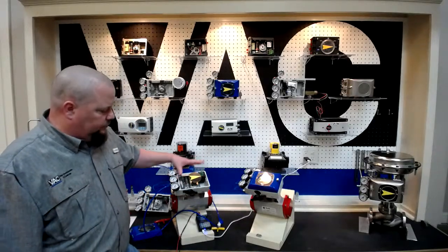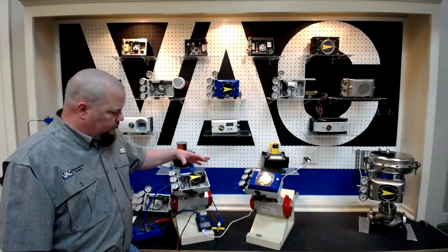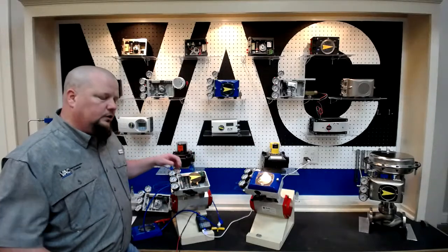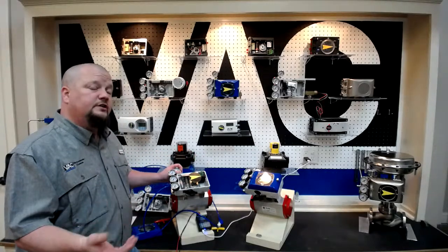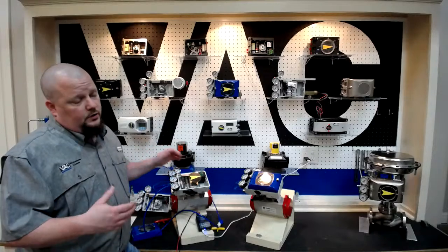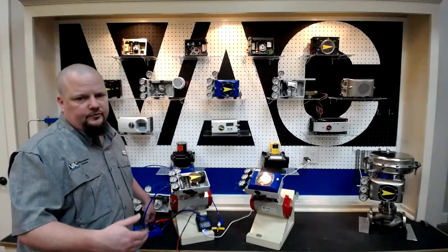So those are things we see a lot on the setup, and what those are basically: no signal, no air, tubed wrong. A lot of times what that's going to give you is as you increase or change your signal, you're going to see nothing happen. It just won't work.